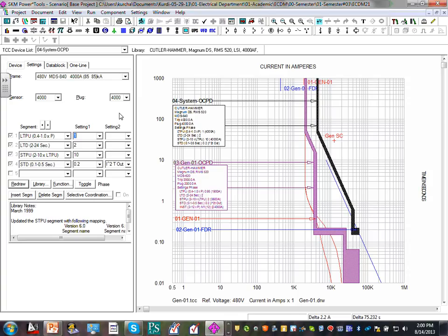Right, but I thought once you got to this level. Oh, that's a $12,000 circuit breaker. I thought I could have 3,983 amps if I wanted in my setting, but you can't. Your balance at that 0.95, the first setting down, doesn't give you that.